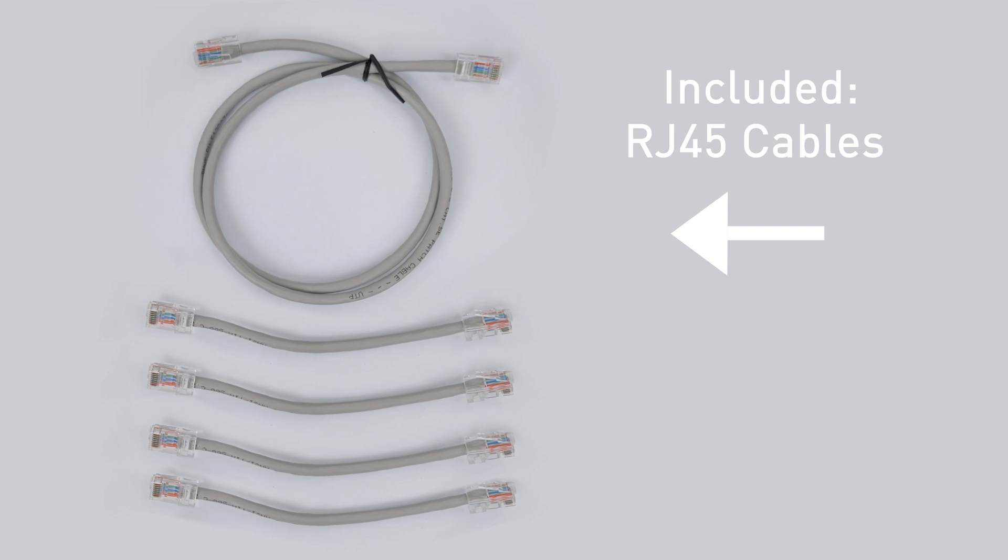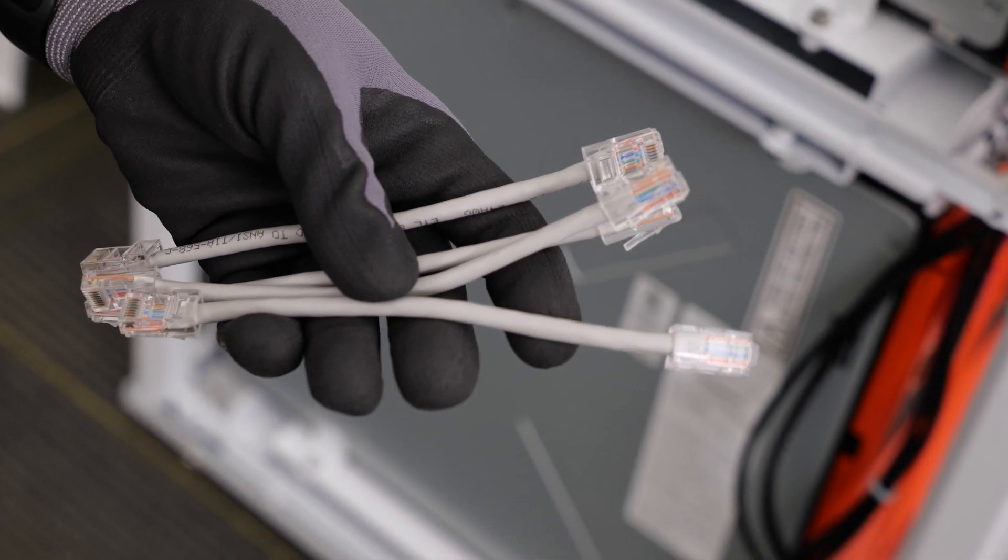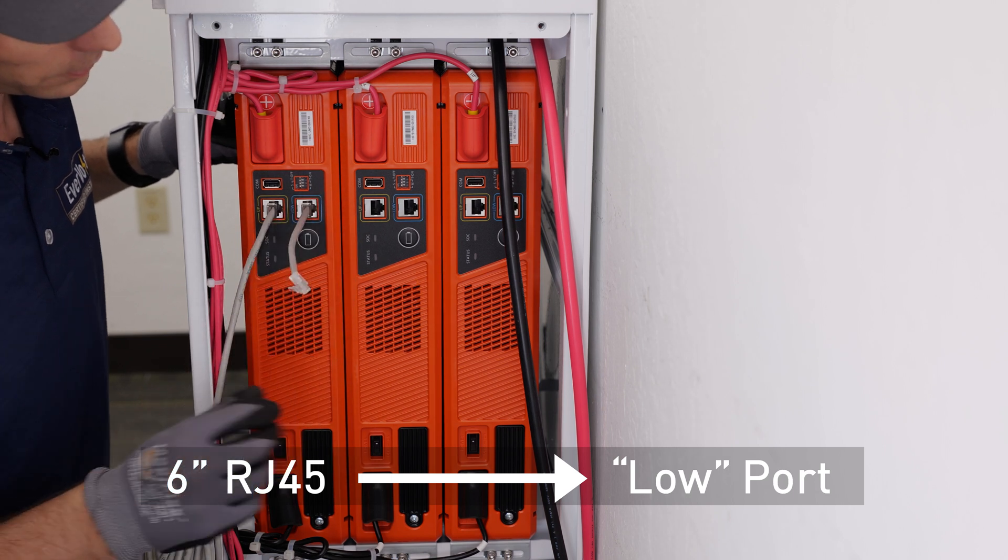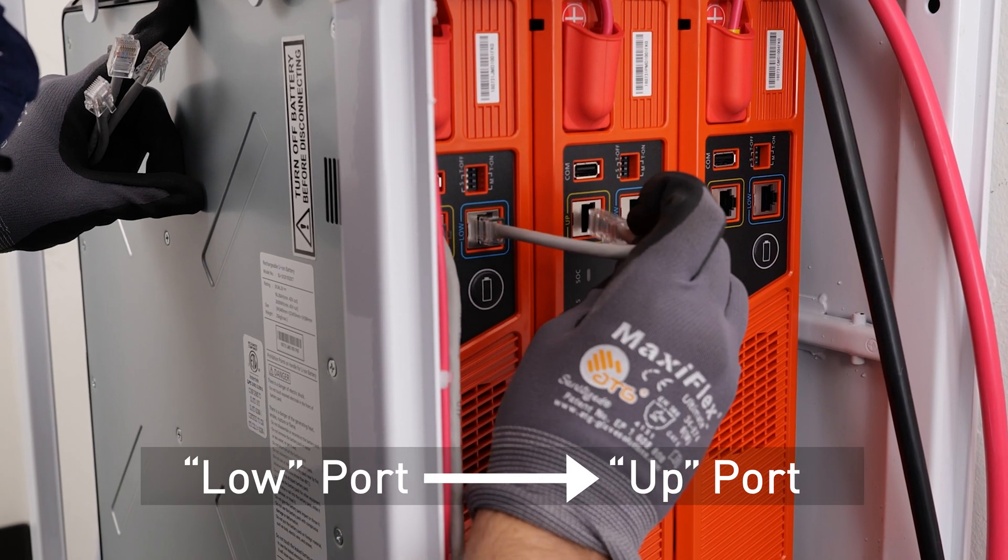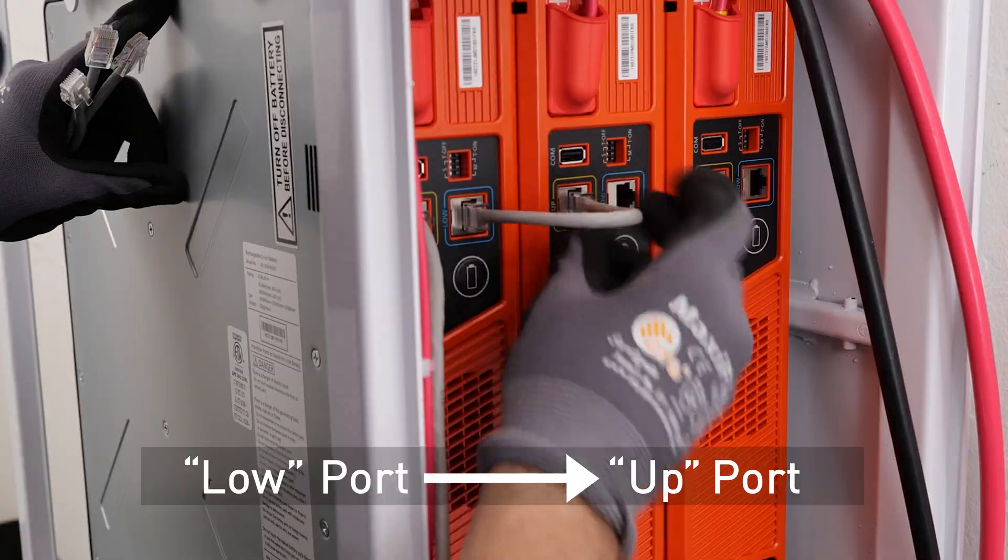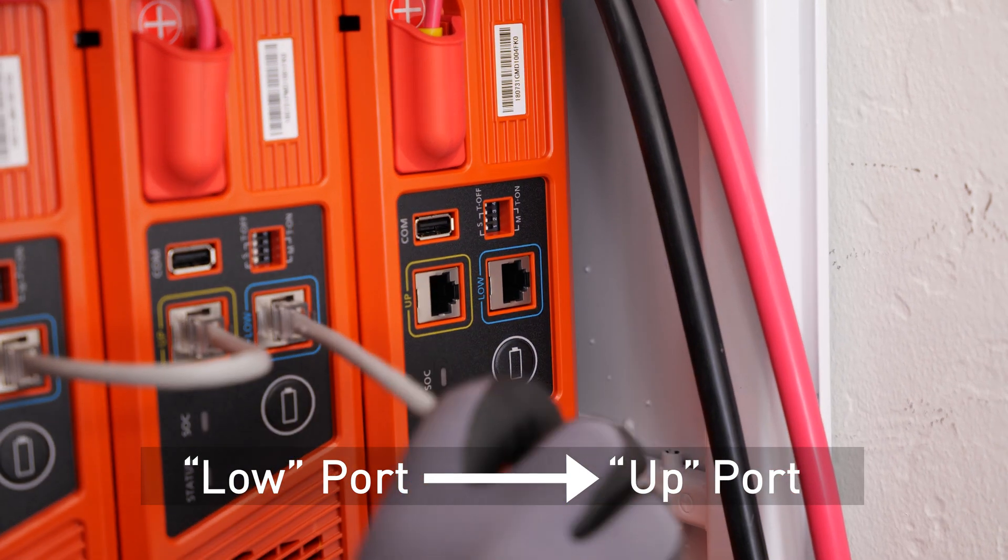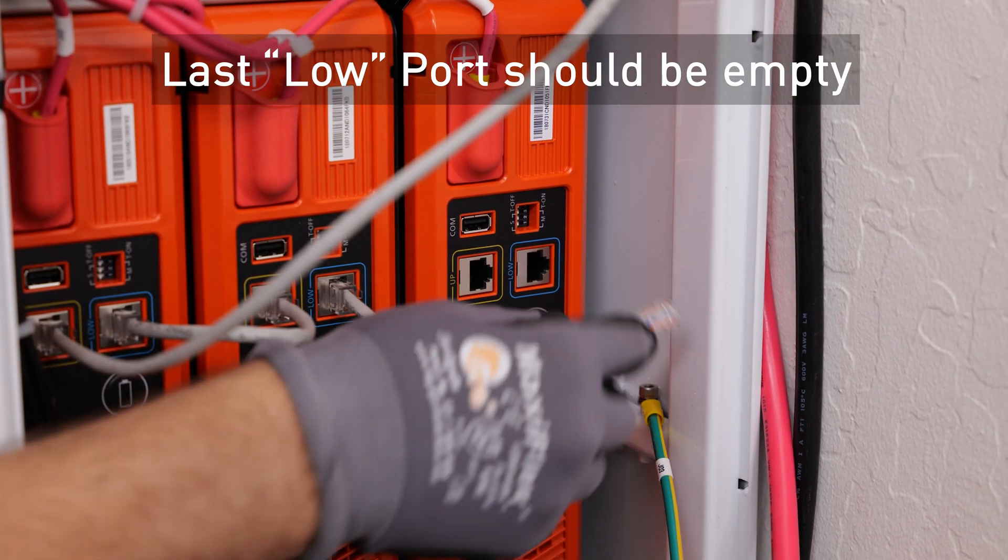Locate the supplied RJ-45 cables for the battery communication. Connect a 6-inch RJ-45 cable from the first batteries low port to the second batteries up port. From the second batteries low port, connect to the third batteries up port. Continue this cascade until the last battery where the last batteries low port should be empty.